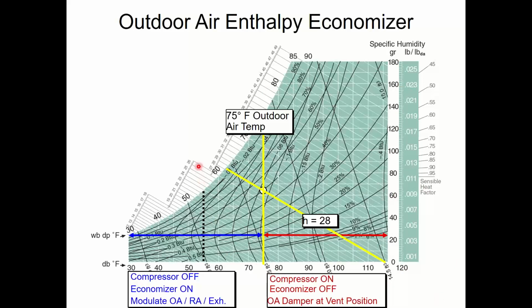If I go to the enthalpy of 28 and I draw that line out, now if it's to the left and below of this, that means it's an economizer day. If it's over here, too hot, non-economizer day. Over here, too hot and too humid, non-economizer day. Over here, too humid, non-economizer day. So I essentially get rid of the triangle of death.